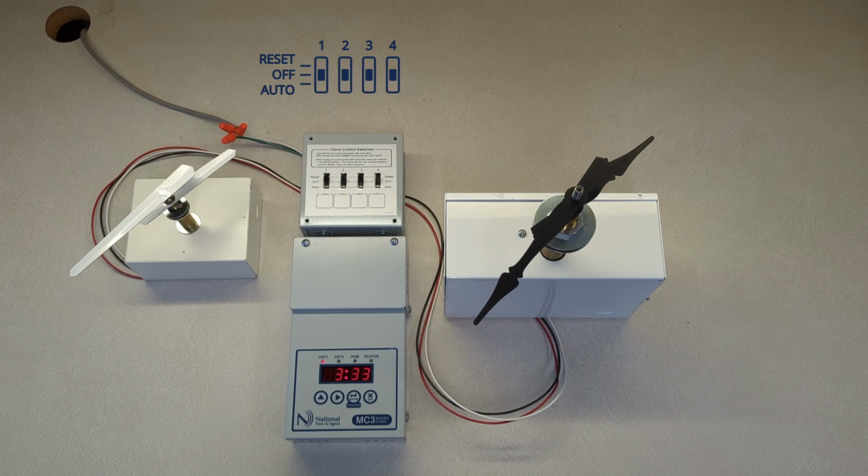With the secondary clocks synchronized, press and release the Enter button to enter the Circuits menu and press Enter again for Circuit 1. This gets you to the Circuit 1 Options menu where we have the choice of On, HH, and Off. Use the up arrow to scroll to HH and press Enter. This menu allows us to tell the master clock where the hands of the secondary clocks are pointing, so that the master clock can correct them.